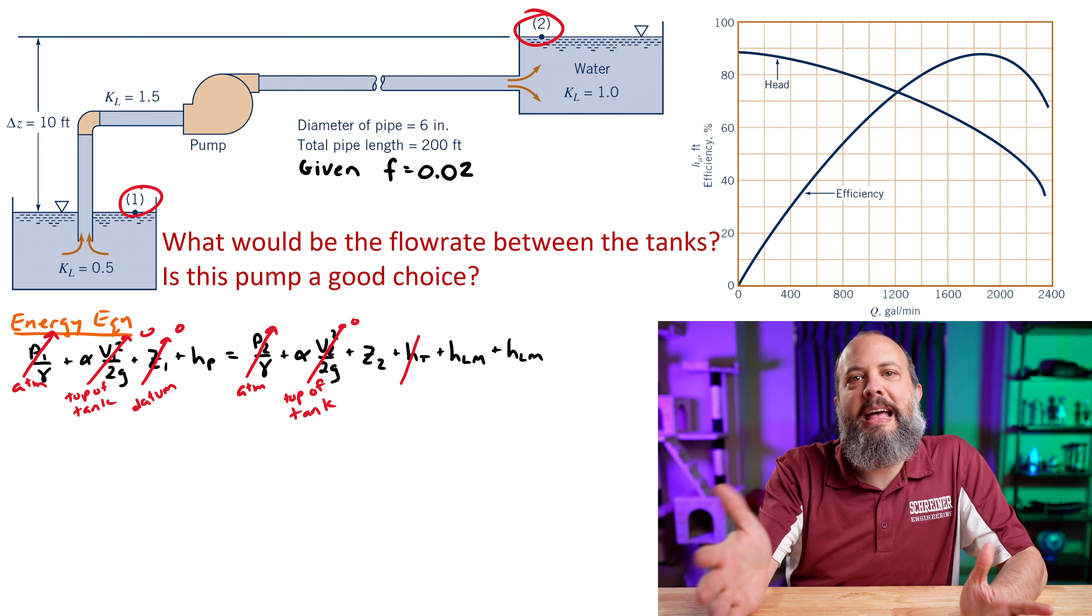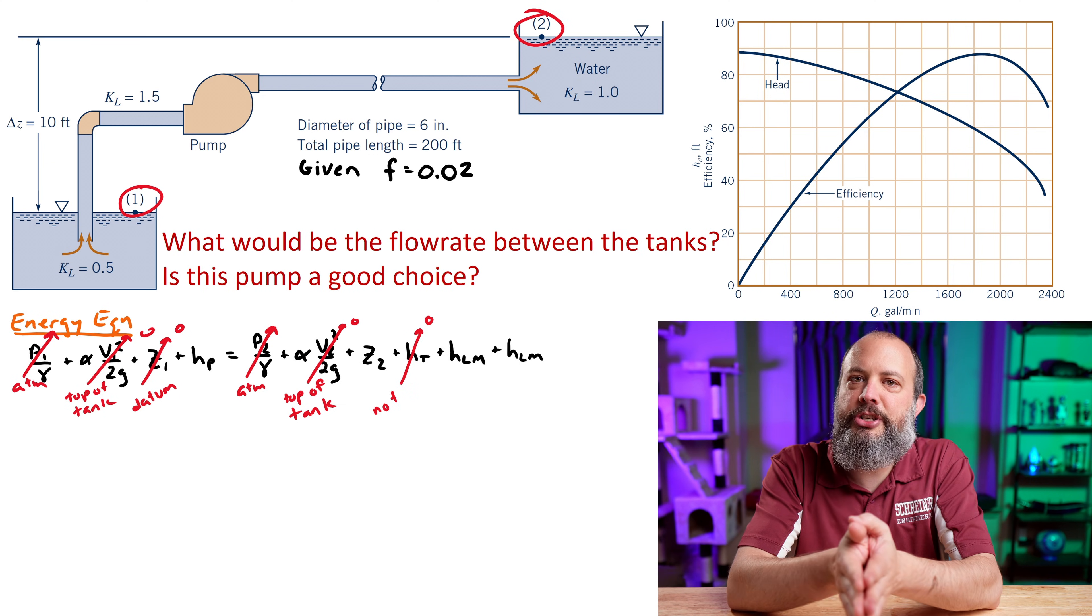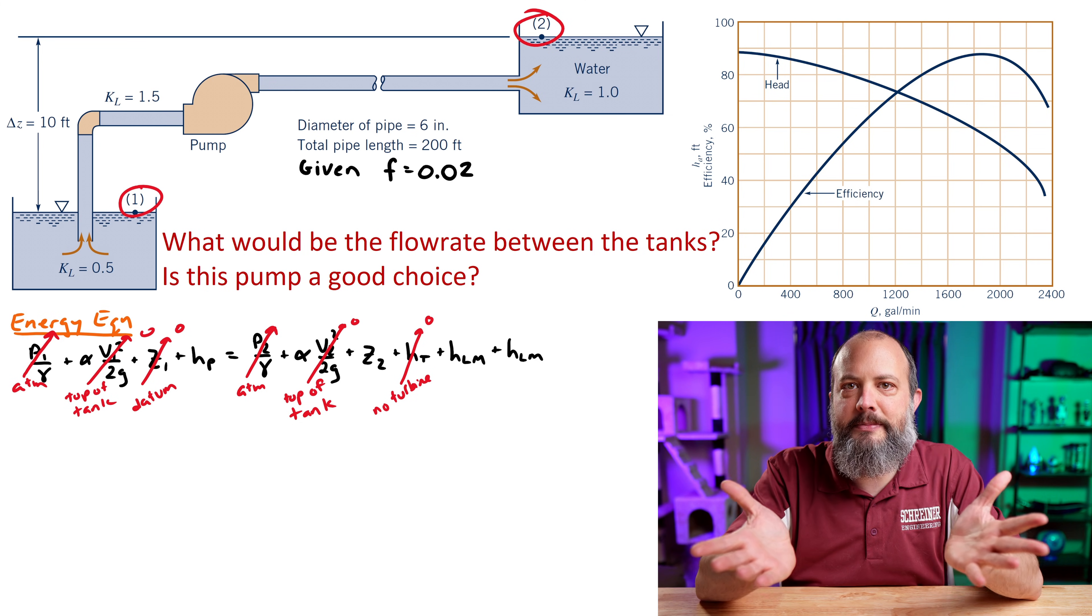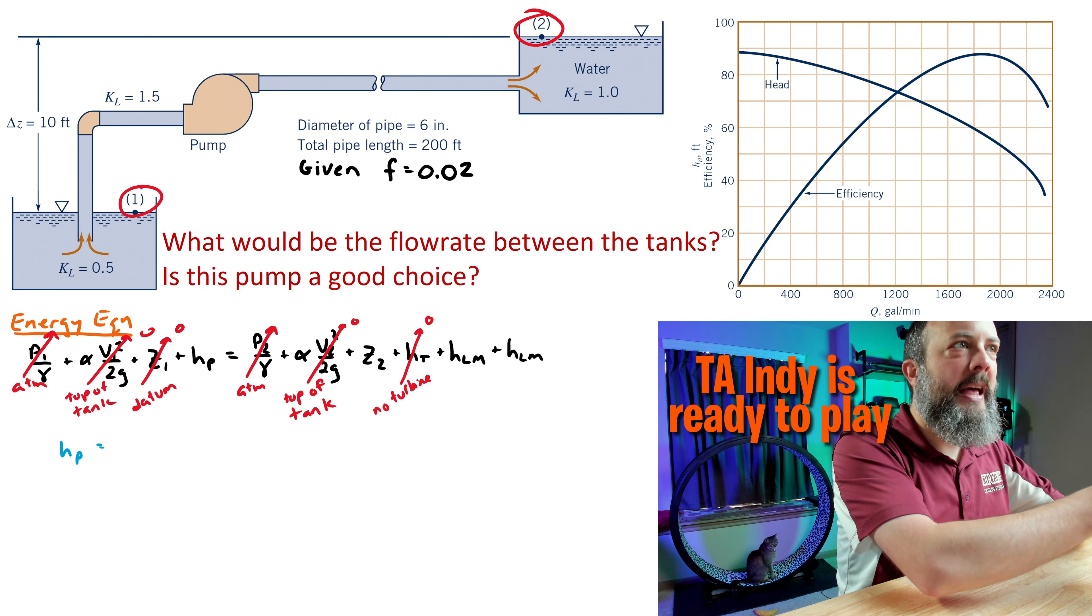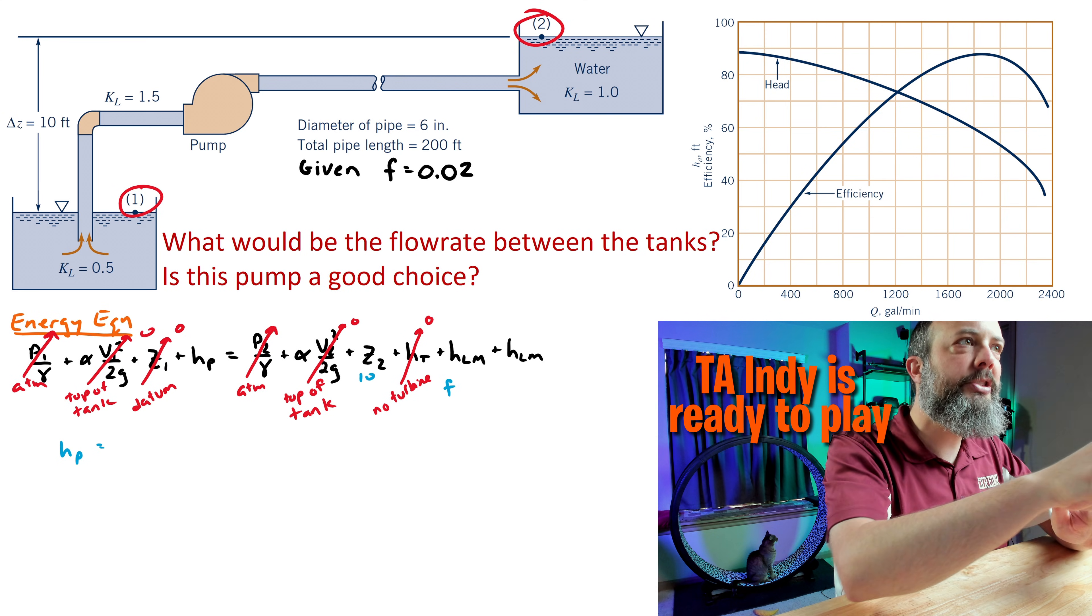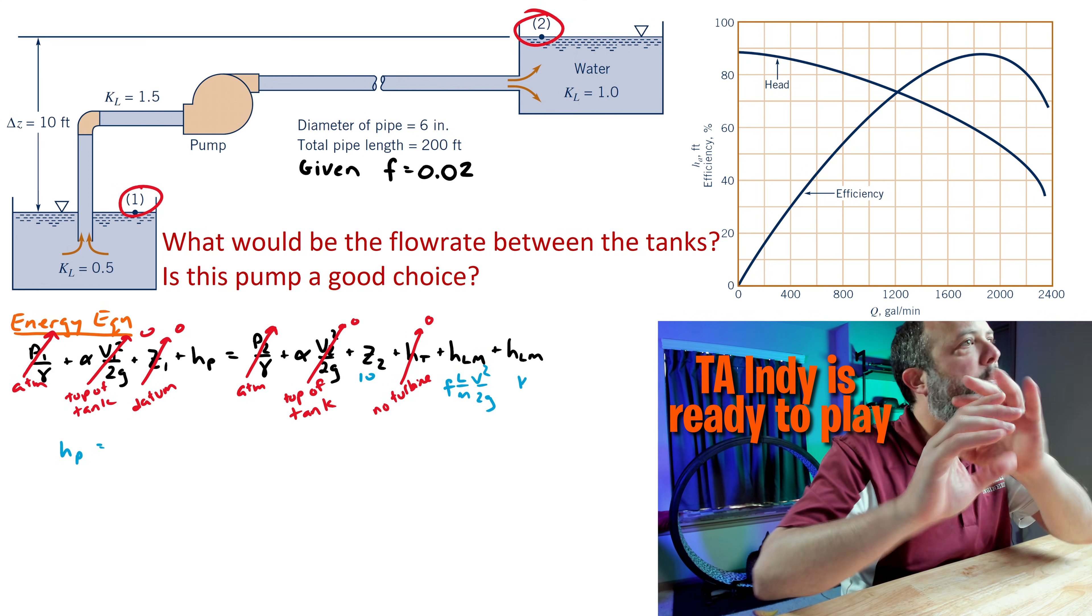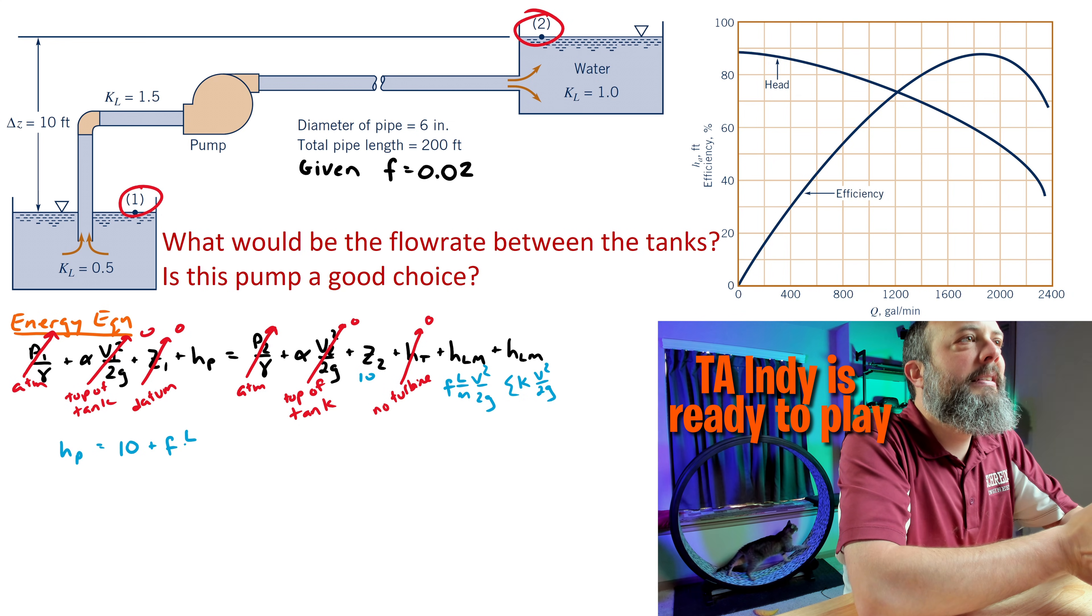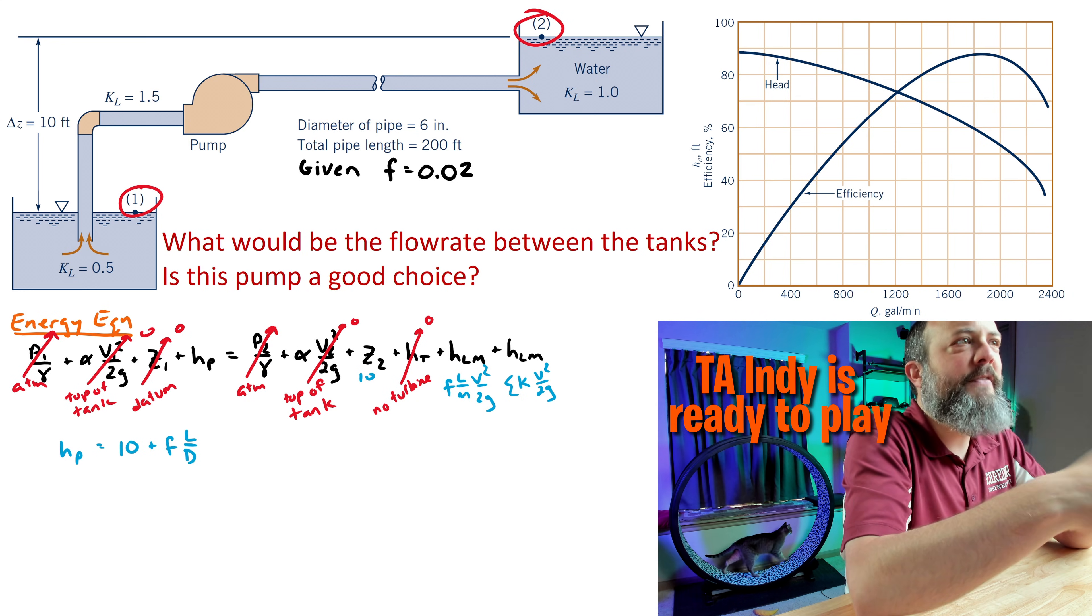I can call my datum 0 at point 1, so I've got a height of 10 feet over on the right-hand side, point 2, and the right-hand side is also where I put my head loss. My major loss is due to friction and minor losses due to all the other stuff, corners and whatnot. After crossing everything out, my pump head is equal to 10 plus my friction term plus my minor losses. The friction term is that Darcy-Weisbach equation.